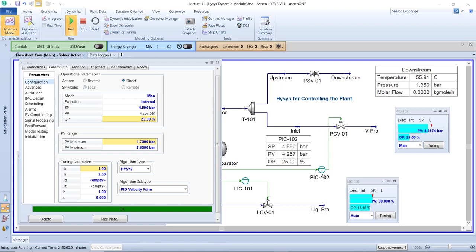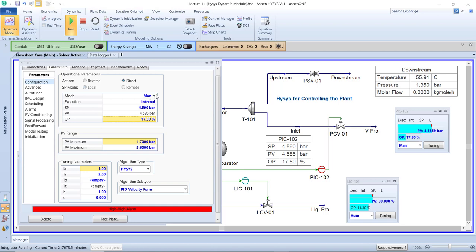When I set the output to 25%, look: the PV is reduced from 4.59 down to 4.28 bar. There is no more high alarm, no more high-high alarm. This is the moment when the control room operator must take action. I want to go back — let me change to 17.50% and then change to bring the pressure back. The pressure increases to 5.0 — perfect. Let me go back to Auto mode.